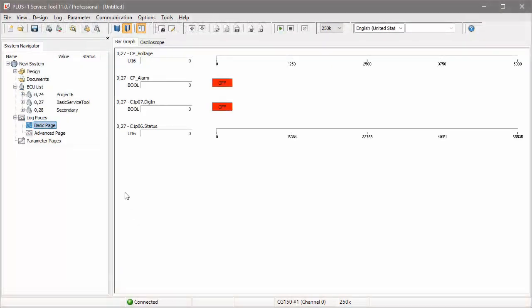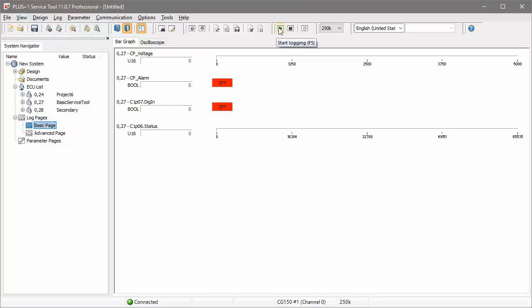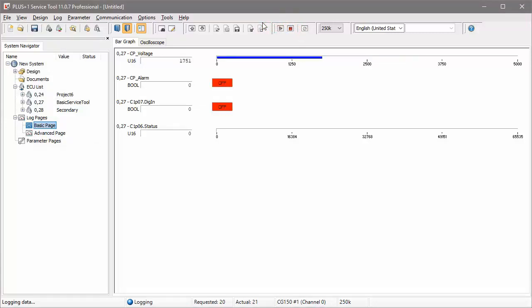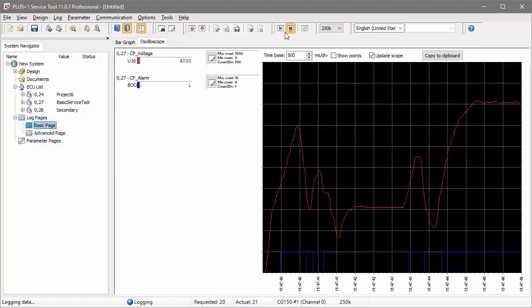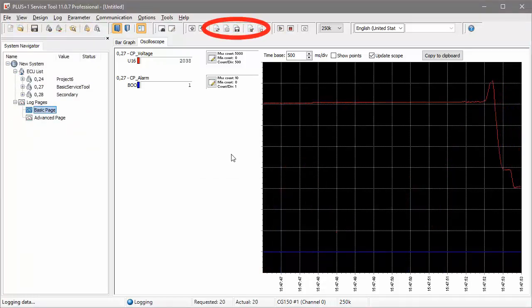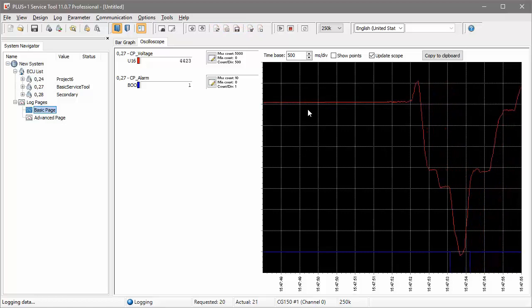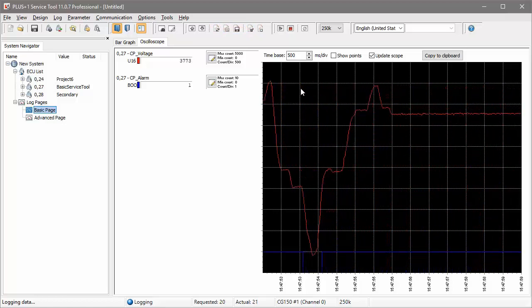We mentioned the difference between Design and Normal mode earlier. Another difference is that in Design mode, you have to click the Start Log icon to start displaying live signal values. In Normal mode, the values will start displaying right away. Also notice that signal values are displayed real-time in the service tool windows, but the icons at the top allow you to also store them in a file where they can be played back at a later time or exported to a CSV file for analysis.